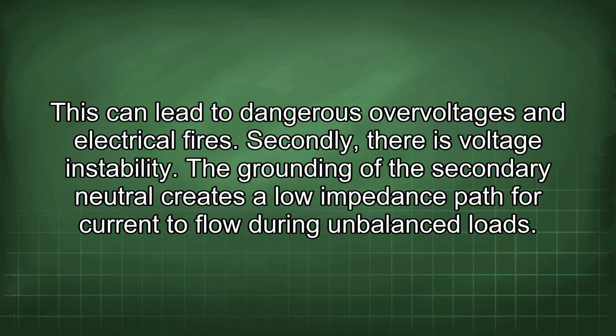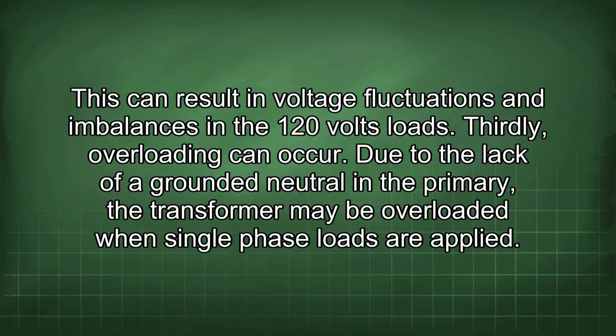Secondly, there is voltage instability. The grounding of the secondary neutral creates a low impedance path for current to flow during unbalanced loads. This can result in voltage fluctuations and imbalances in the 120 volts loads. Thirdly, overloading can occur. Due to the lack of a grounded neutral in the primary, the transformer may be overloaded when single-phase loads are applied.